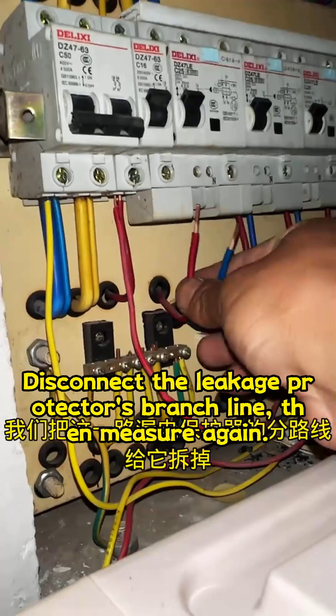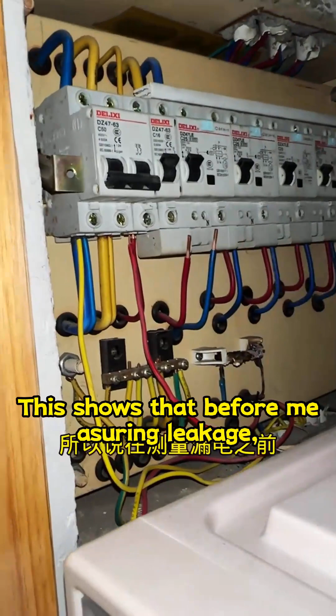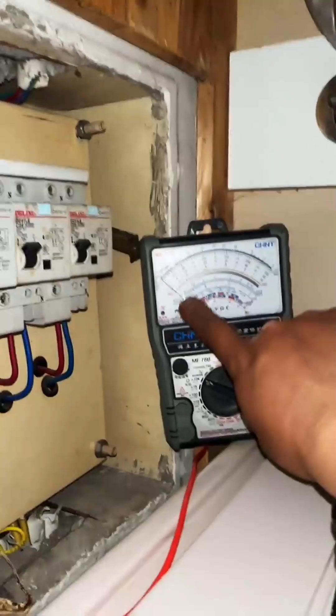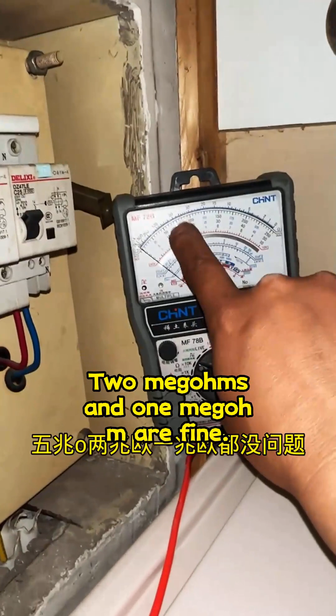Disconnect the leakage protector's branch line, then measure again. Again, place the black probe on the ground bar and measure the hot and neutral wires. Now the needle does not move. This shows that before measuring leakage, the wires must be disconnected. The needle shows 5 megohms. 2 megohms and 1 megohm are fine. Any reading below 0.5 megohms indicates leakage.